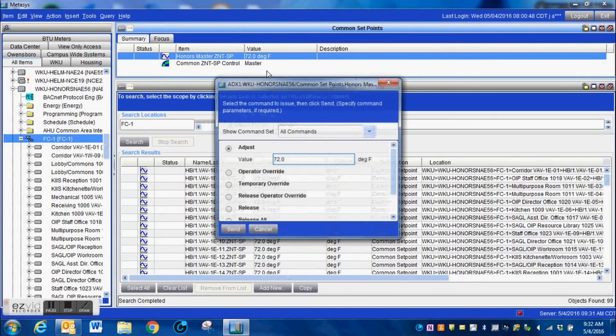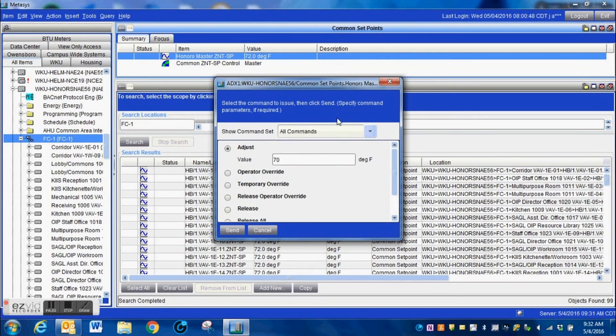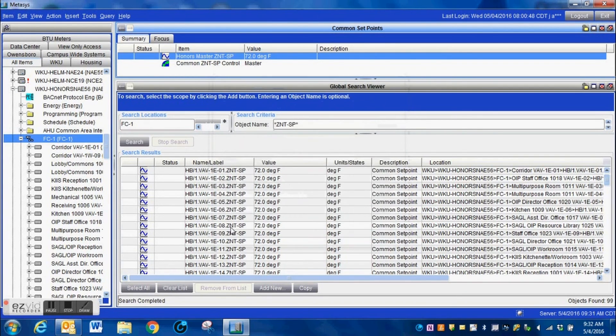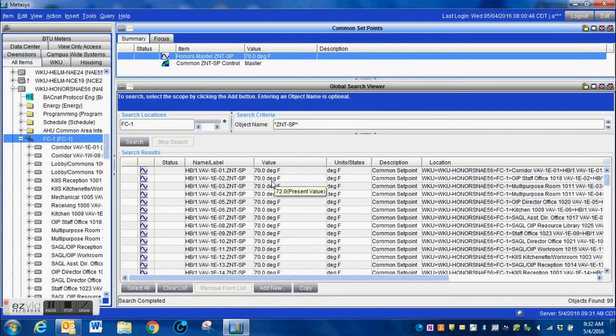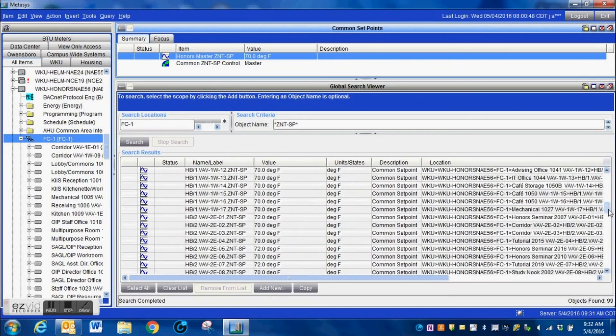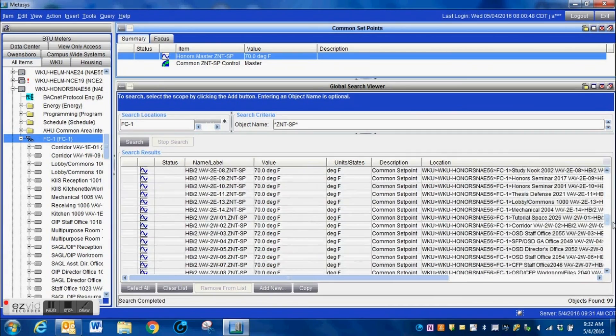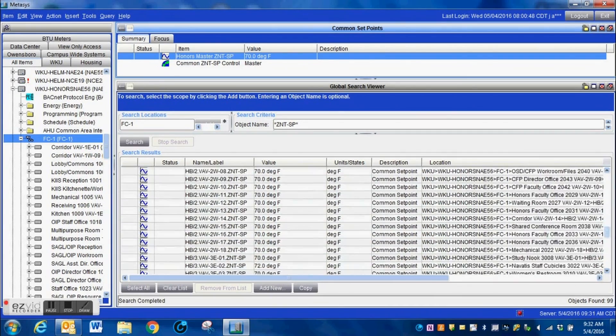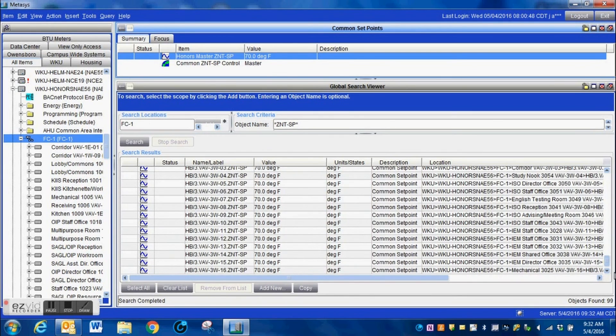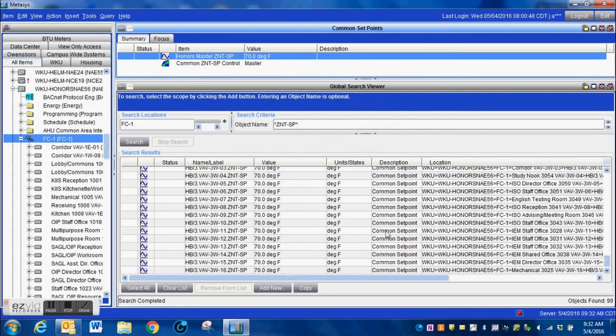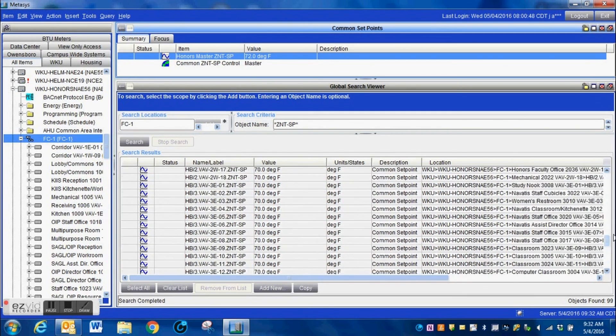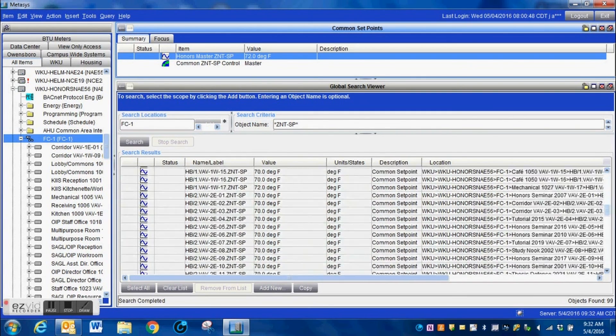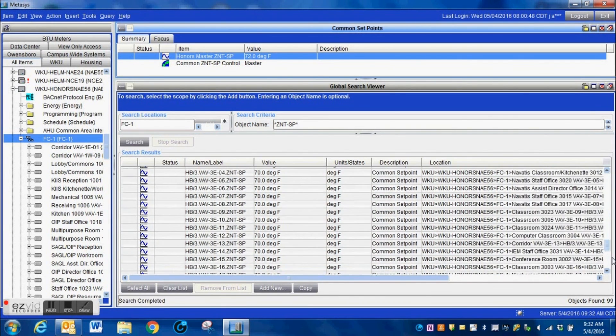What we're going to do here, I'm going to command the value and our master value. Once I press the send button, you will see it broadcast that new set point to all of these VAVs. It takes it a few minutes. It will follow that slaves list and go one at a time down through there. It's not something that is instantaneous to any of them, but it is just one at a time is how that it will write to those. I'm going to go back here and I'm going to change that back. It's very powerful tool. You might want to check it out. It's something that I know that you will use. It's very powerful. You can see here that it is changing the values that they're all following the master point.